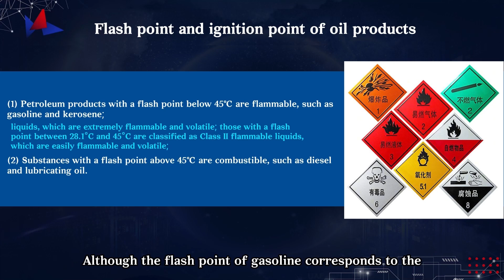At their flash point, the vapor concentration of kerosene, diesel, and lubricating oil reaches the lower explosive limit of that product. Gasoline is different. In a sealed container at room temperature, its vapor concentration already exceeds its upper explosive limit and won't flash due to lack of air. Therefore, it is necessary to lower the temperature of gasoline to reduce its vapor pressure until the mixture can flash.